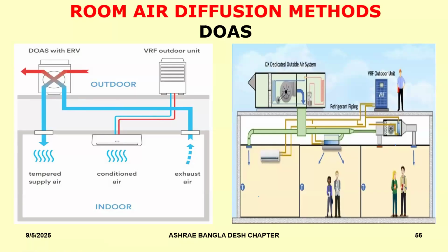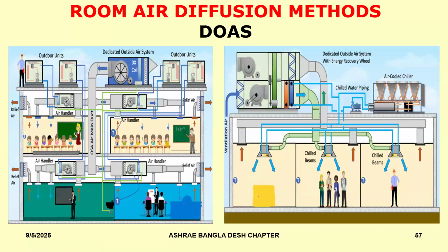This can get more complex as the building gets bigger and bigger. For example, here is one situation like that, where we got outdoor units which are catering to all the spaces, and you have one dedicated outdoor air system which is bringing the outside air, treating it, and then supplying it to the various floors. Now, you can decide how much of this should go into each space depending upon what is the actual requirement.